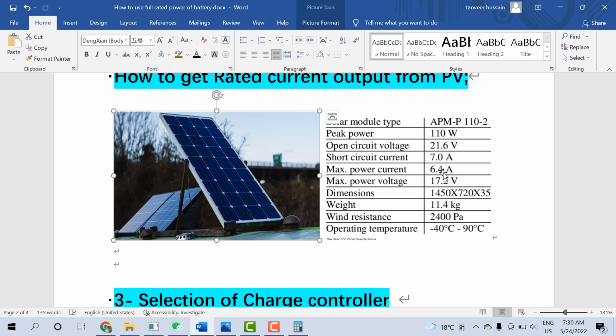So if you need to measure the current and you're not getting 6.4 ampere, then you have to again find the voltage drop near the panel. Sorry, not voltage drop - you need to measure the voltage near the solar panel, how much, and then you should measure the voltage at the other end of the cable, for example near the solar charge controller input. So if the voltage drop is higher, same as in the first case, it means your cable quality is not good or the cable length is too long.